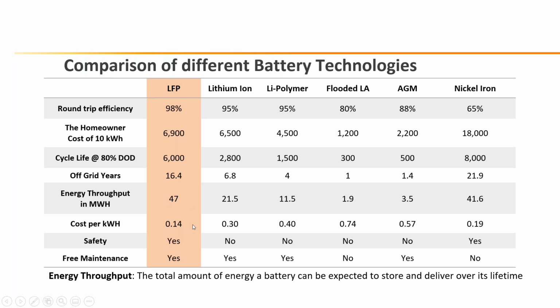So this is really what you're paying per kilowatt hour. And LFP has one of, if not the, lowest cost per kilowatt hour because of the longevity of the chemistry itself. LFP is also very safe and free of maintenance, like I mentioned before, and has 16.4 years of off-grid usage. So the only one that would be comparable to that is this nickel iron, but when you then compare the round trip efficiency and cost, I think we can all see here the LFP battery is definitely one of the most competitive and probably the one I would recommend for most project applications.